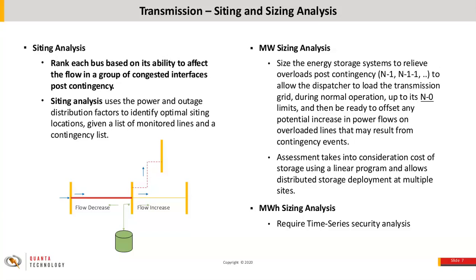Sometimes just knowing there's an overload for 4 hours on a given day might suggest a 4-hour storage design, but if that repeats as part of a peak week and there isn't enough grid capacity to recharge the battery, you need to oversize the battery to ride through the whole week.